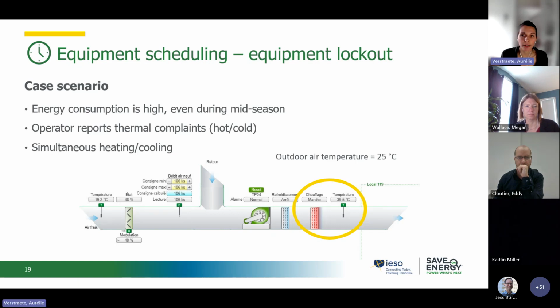Here we have an example to illustrate the opportunity for equipment lockout. During your investigation, you analyze energy data and you see that energy consumption is very high, even during mid-season. The operator said that he received many thermal complaints, hot and cold, and also the BAS graphics review shows that you have simultaneous heating and cooling.